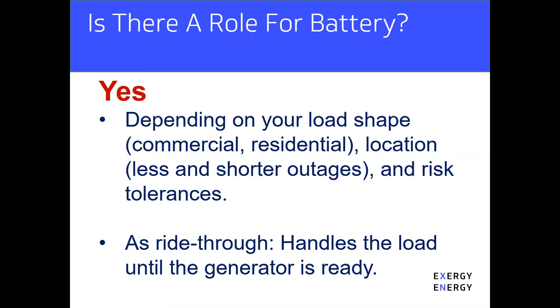I'm sorry to interrupt, I got to make sure I heard that correctly—did you say 7 seconds? Yes. Wow, okay. At that point, technically you can accept a full load transition and the generator will stay online and respond. But if you have a battery in the system, it would certainly be advisable to do a ramp load scenario where you slowly ramp the load over, but still within a minute would be a very conservative number.